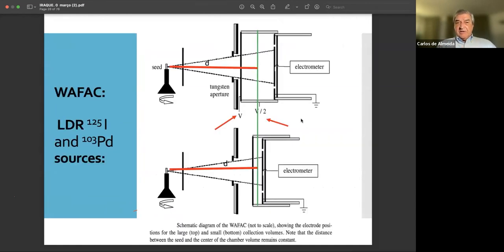When you talk about iodine-125 and palladium-103, you use the wide angle free air chamber, which means a chamber that is very wide. You can see here, this is the source. Then we have a distance to the center of the sensitive volume. Here are the two guard rings, and these are the electrodes, connected to the electrometer. Then you get the walls close together, but you keep the distance from the source to the center of the collecting volume the same. This is a very sophisticated system, even more sophisticated than the free air chamber, which has existed for more than 50 years. The wide angle free air chamber is something recent.